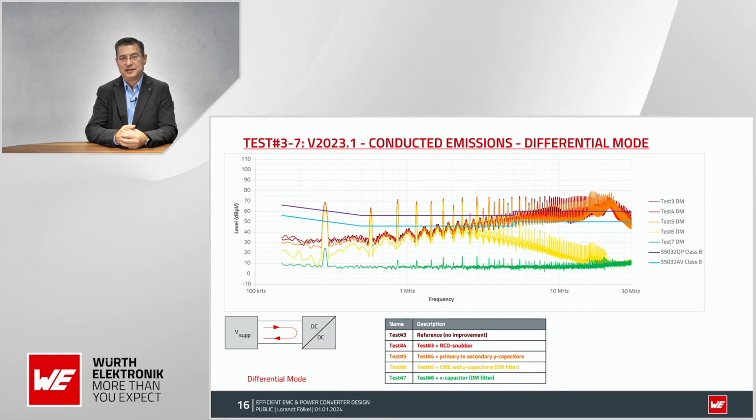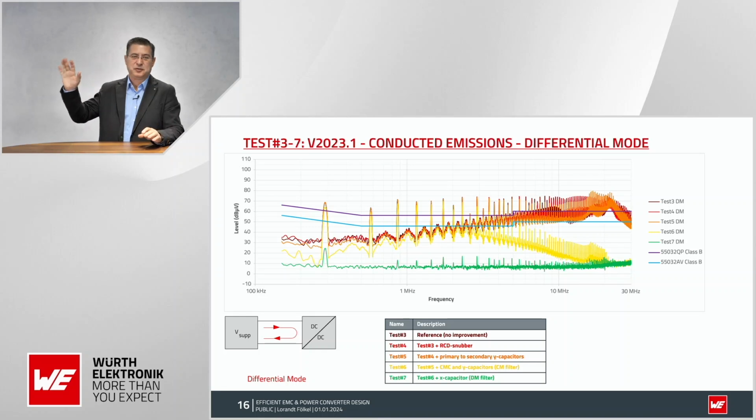Look to the EMC guy, because he will be impressed. He will congratulate you, and he will first check if his machinery is really working. Because when you have these low limits, low peaks at just the noise floor, he starts to be afraid that he didn't measure something correctly, or the antenna is not connected, because this is very, very rare. When you reach this level, some EMC guys even print it out in A3 format and put it in the chamber and say, look, it's also possible. Try to achieve this measurement, because this is something very rare.